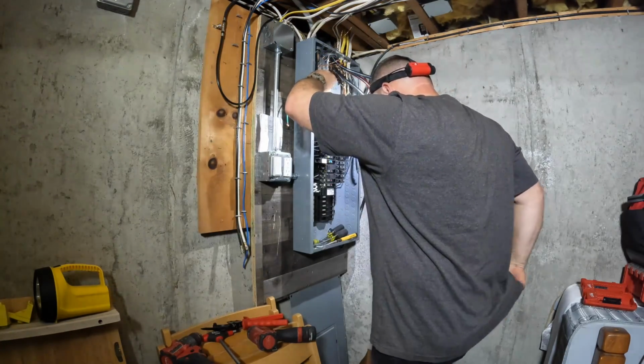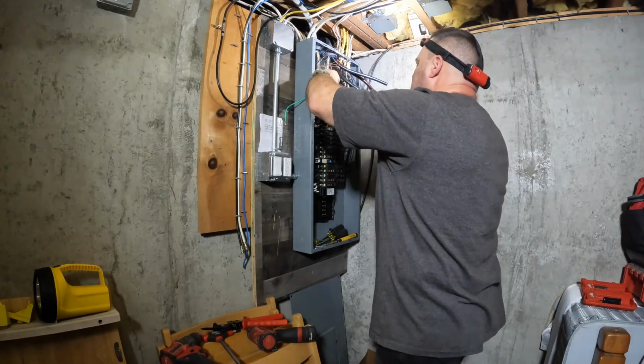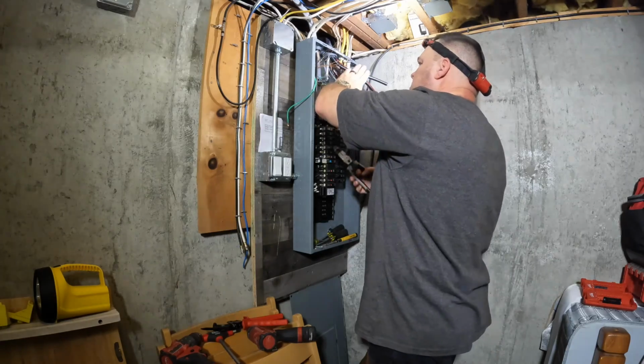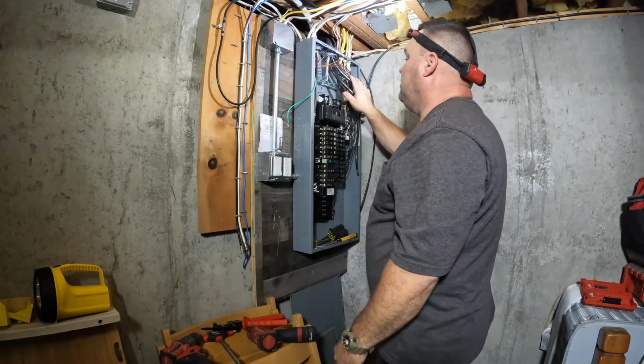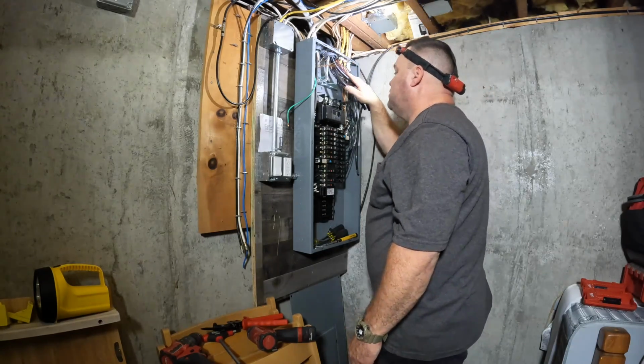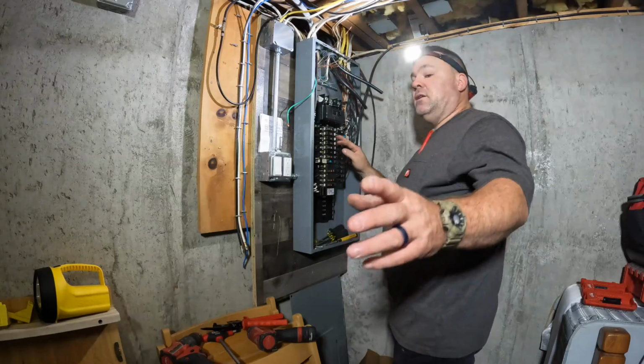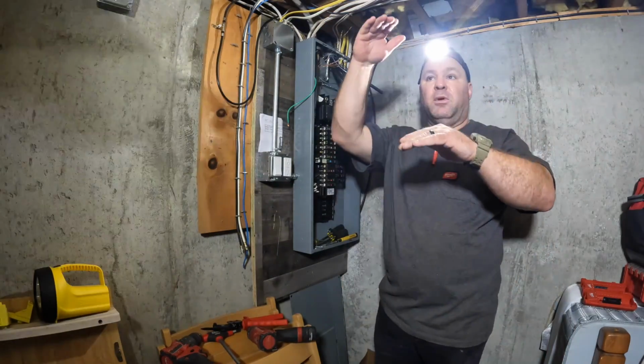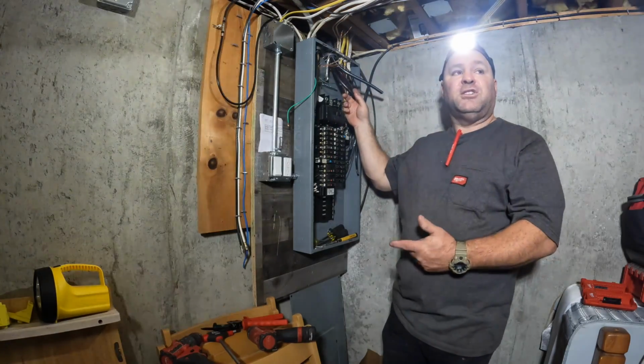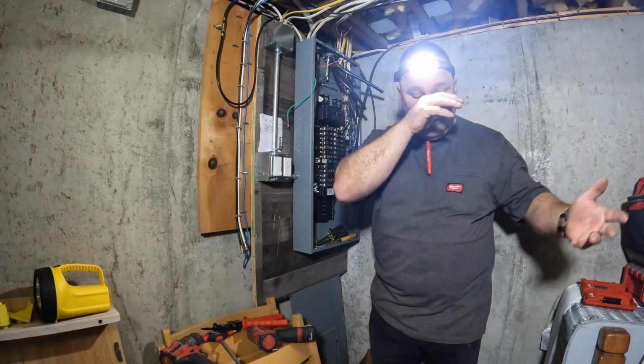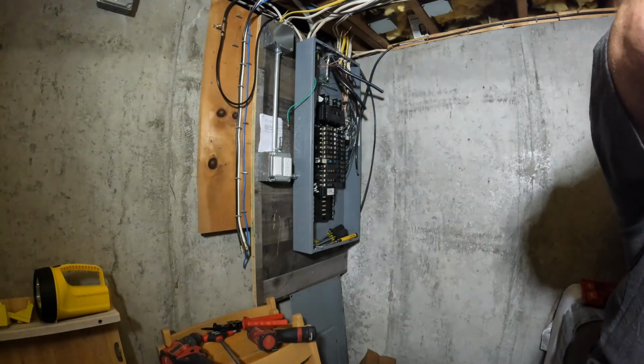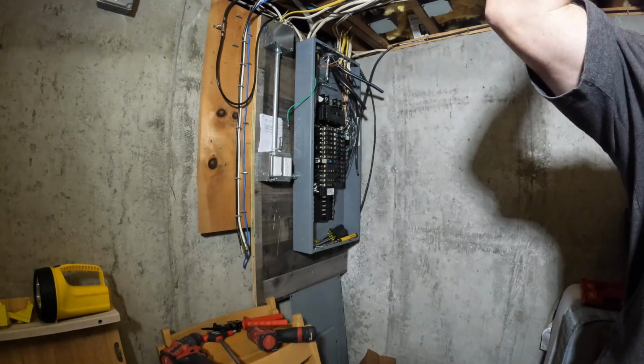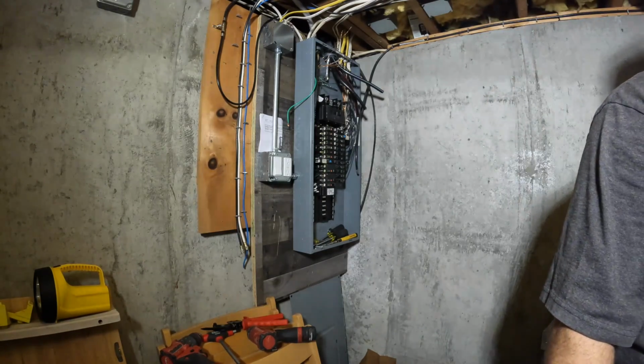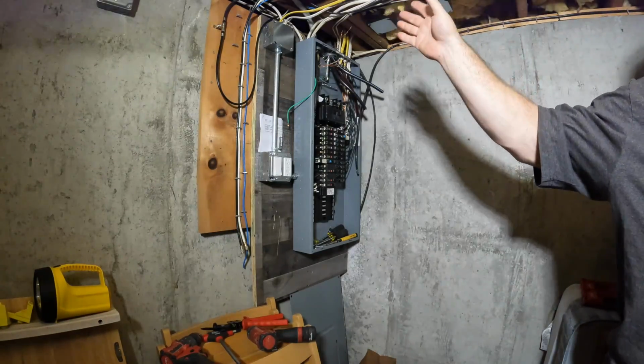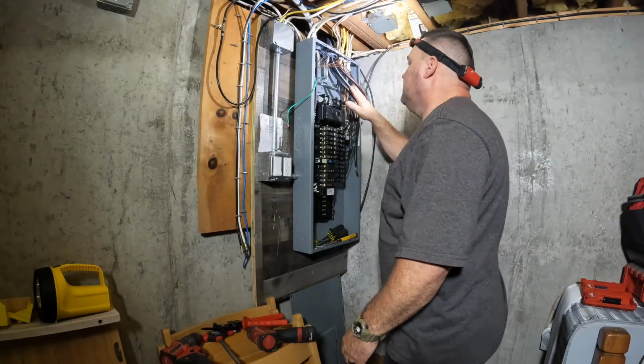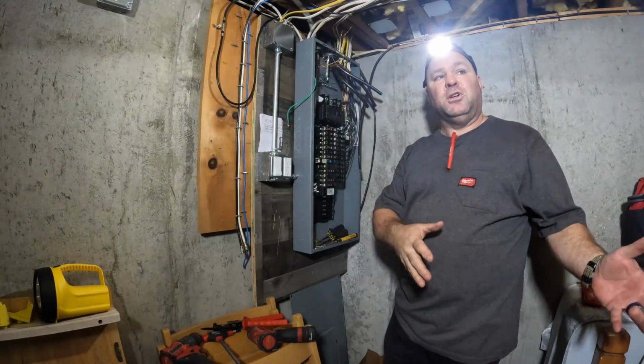This cable here that you're basically working with now, is that system out to the generator, or is that generator back to the panel? This is the utility power. Right. I'm sorry, this is power from the transfer switch to supply the power to this. Right, and then this wire right here also goes to the transfer switch. Right. And when it goes from utility to generator, it energizes the same set of conductors from a different source. Right. So you have the generator, this is your live wire from the generator. And then you also have live power from the street. Yeah, this is coming from the generator. Correct. It's going to power the transfer switch when the utility loses power. So these wires are always here, like this, but they're either going to be powered from the utility or from the generator. Exactly.